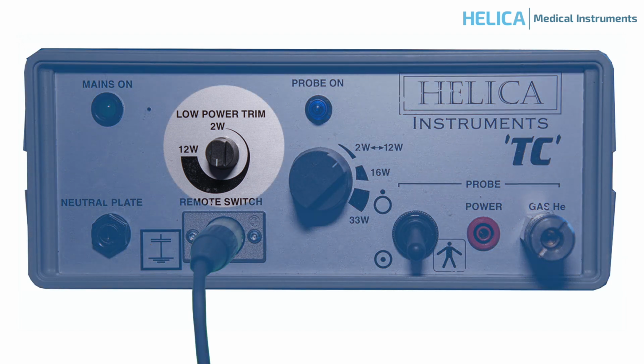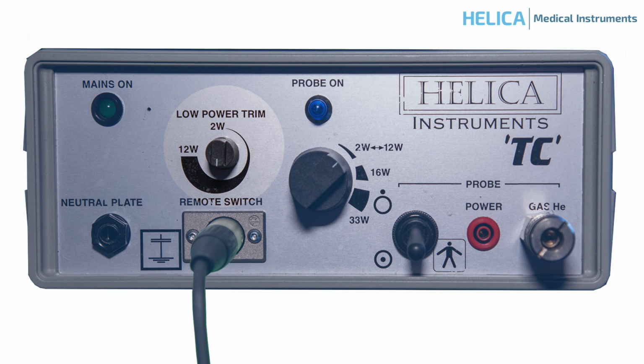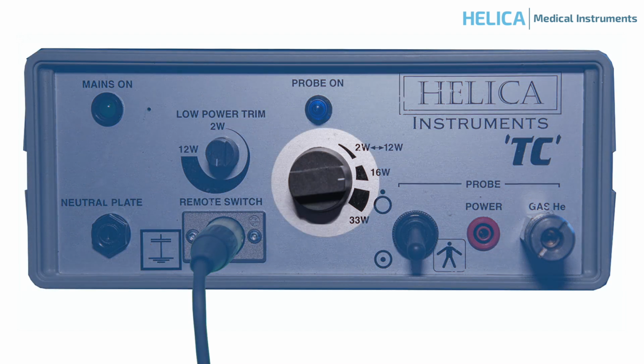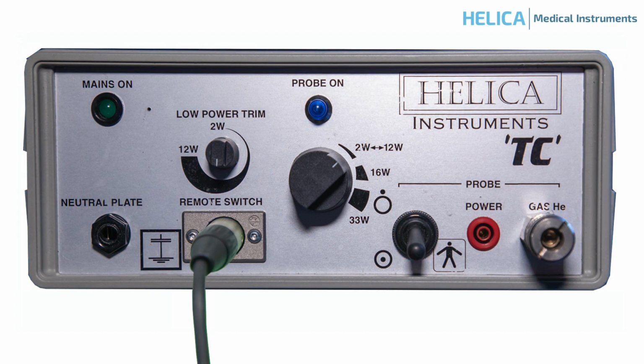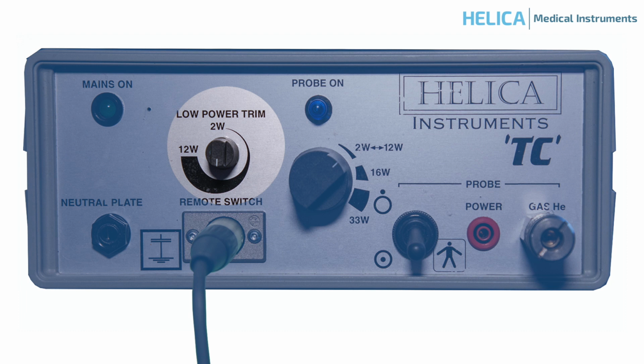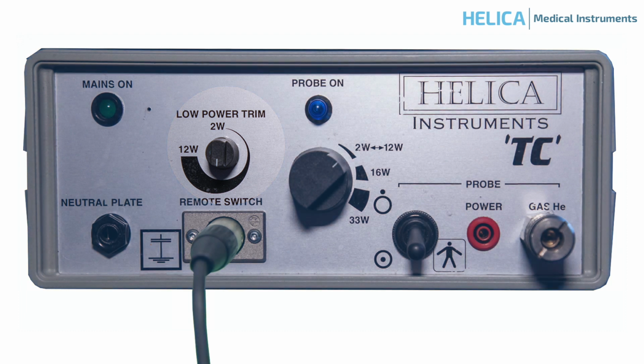The trim knob controls the power settings required for all laparoscopic procedures. The lowest power setting is between 1 or 2 watts and 12 watts. The power is increased by turning the knob clockwise. The trim knob will operate only when the main control switch is in the low position. Most laparoscopic procedures are begun with the trim knob at the 6 o'clock position, i.e. about 6 to 8 watts.